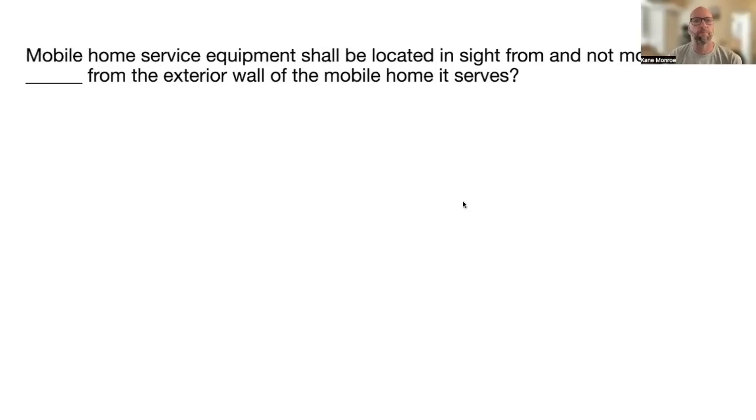Mobile home service equipment shall be located in sight from and not more than 30 feet from the exterior wall of the mobile home it serves. NEC 550.32(A).